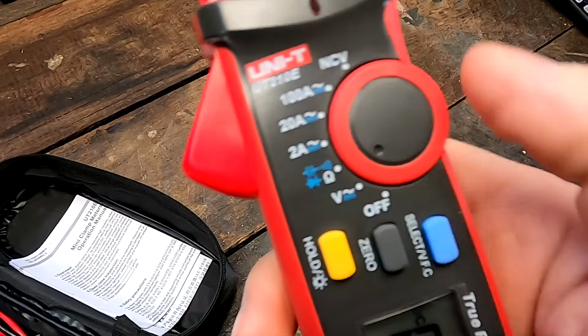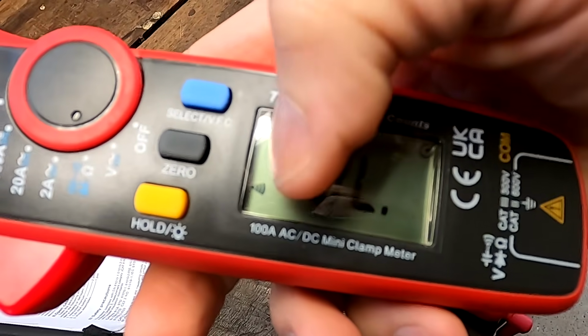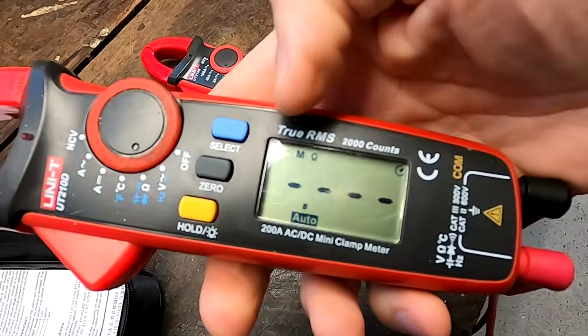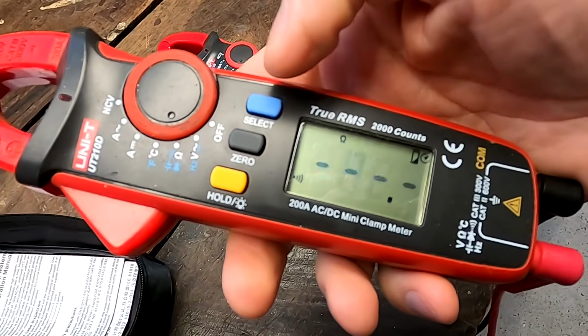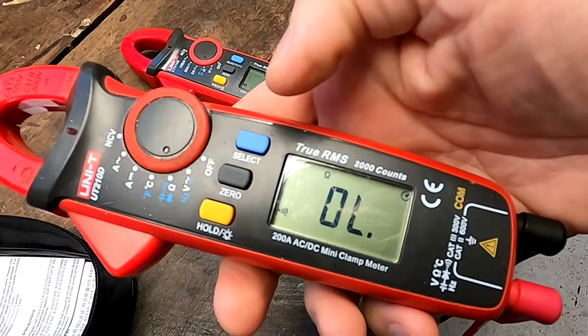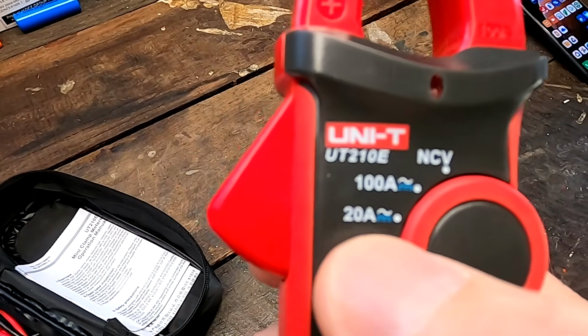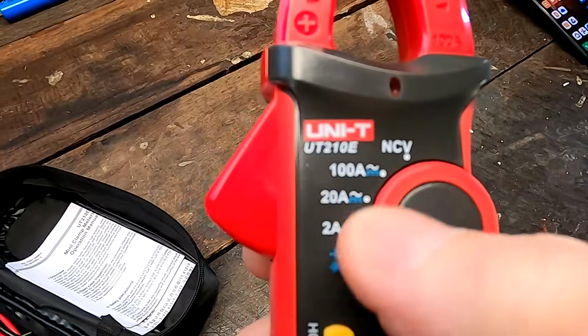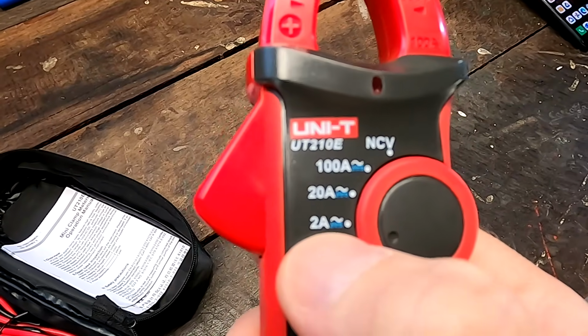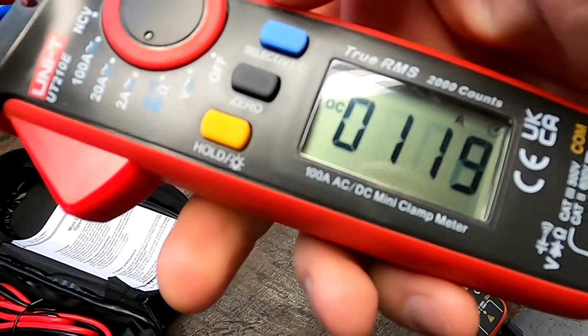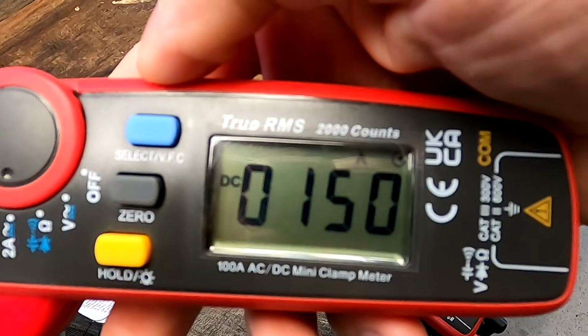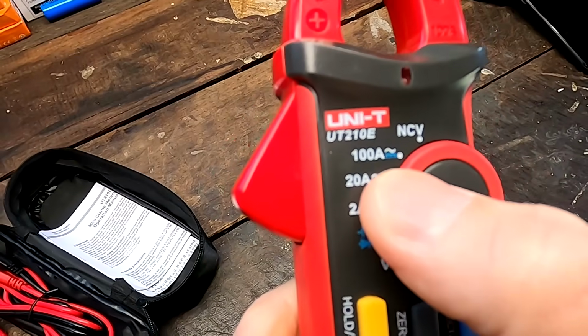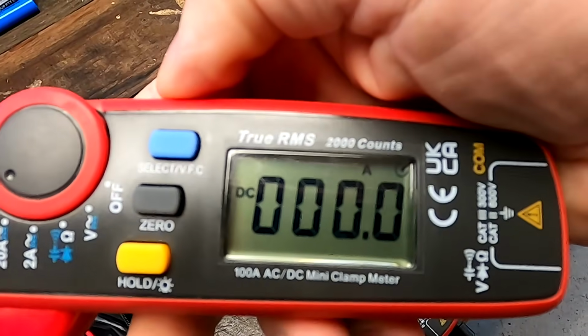If we select resistance, it starts in continuity test mode. On the old one, it measures resistance and I have to click select to go into continuity mode. With this device we also have the 2, 20, and 100 amp ranges, which have all been modified. The 2 amp current selector gives us a very fine resolution of 1 milliamp, so we can actually use this device to measure the micro amps of balancing currents in these BMSs. Also the 100 amp selector now goes up to 100 amps.